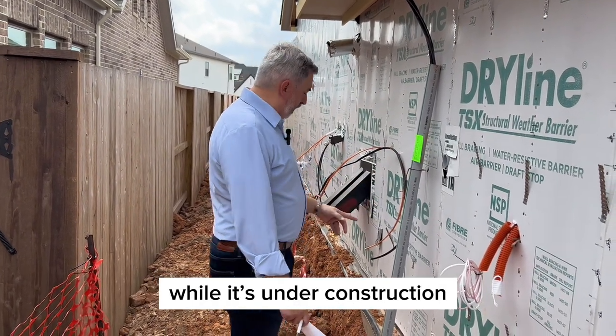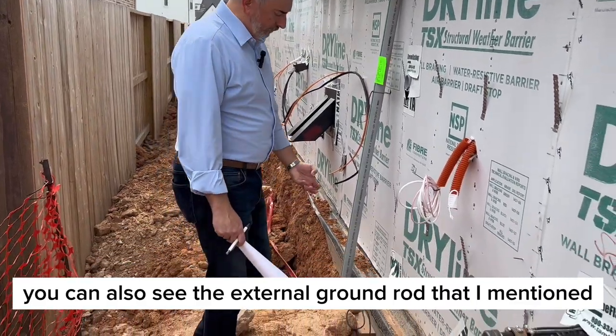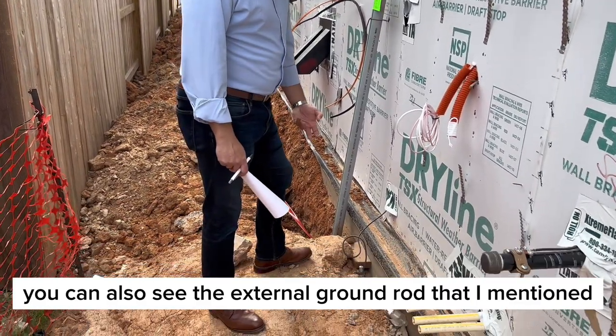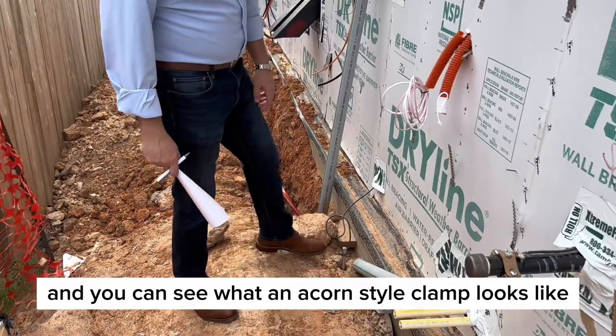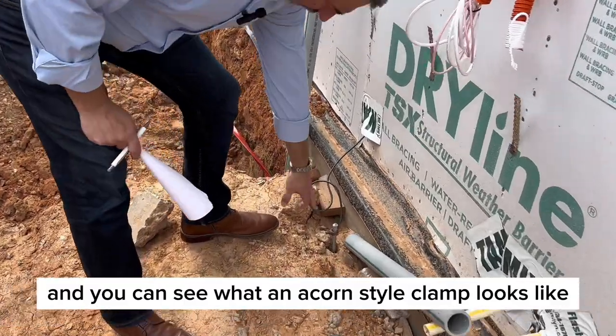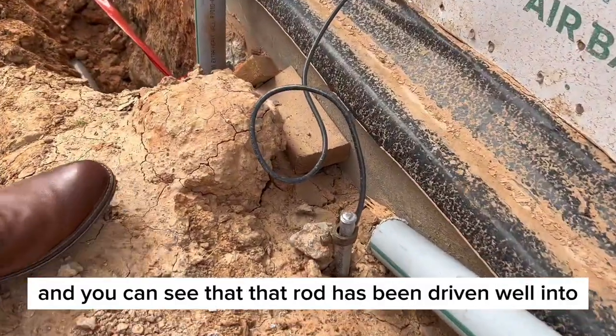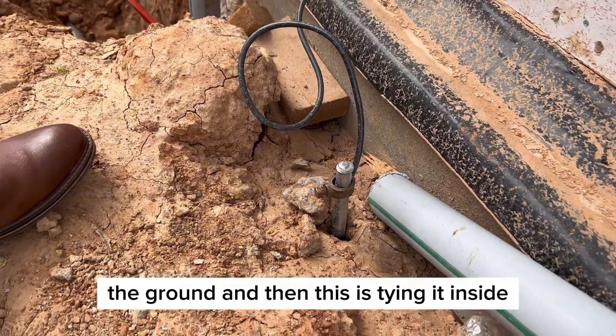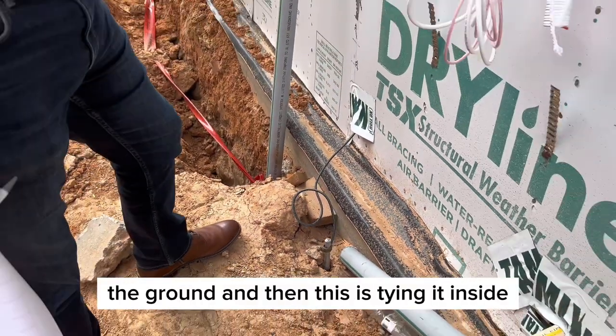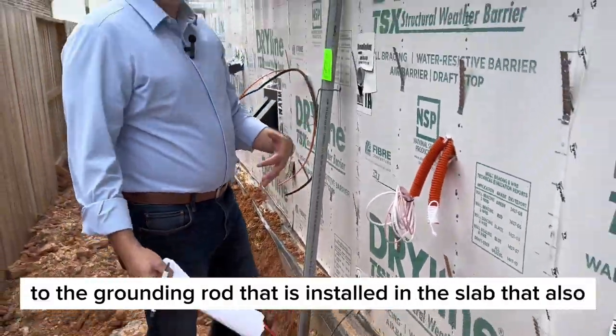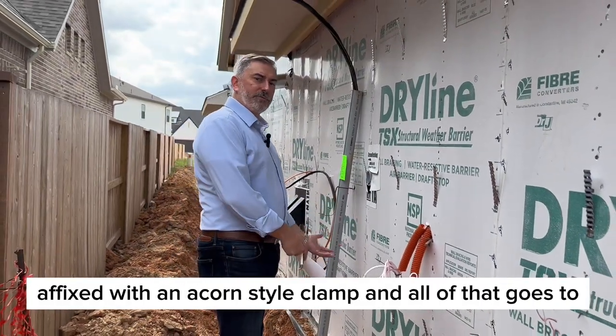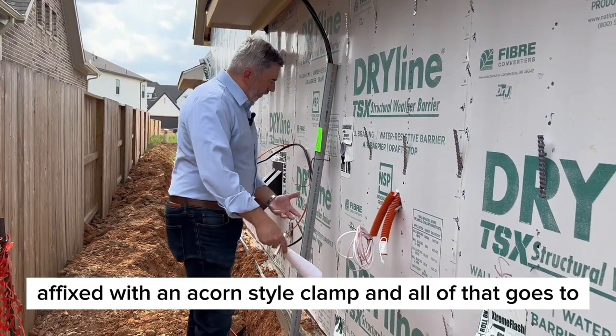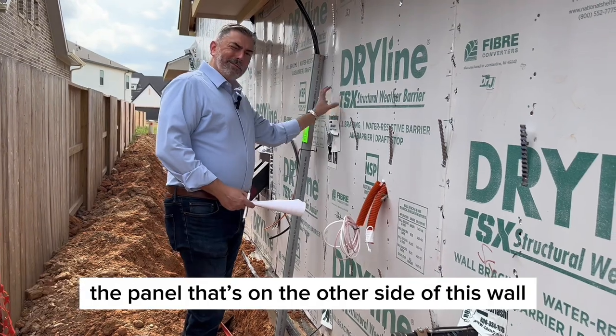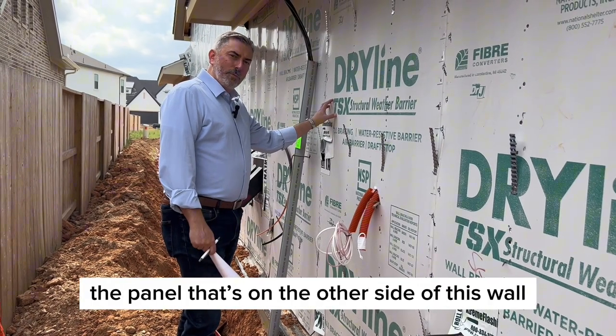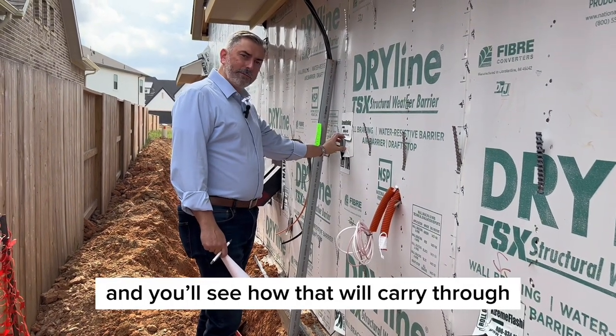They're probably going to set a temporary meter on the outside here to supply service to the house while it's under construction. You can also see the external ground rod I mentioned earlier, and an acorn style clamp, with the rod driven well into the ground, tying it inside to the grounding rod installed in the slab, which is also affixed with an acorn style clamp. All of that goes to the panel on the other side of this wall, and you'll see how that carries through.